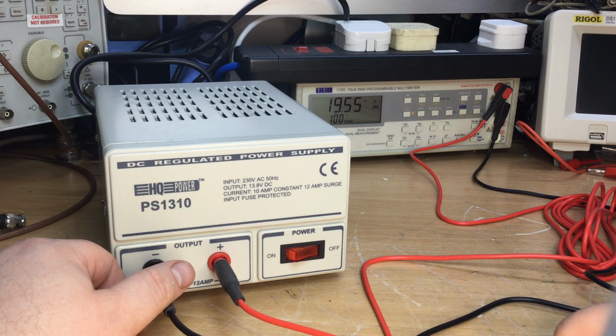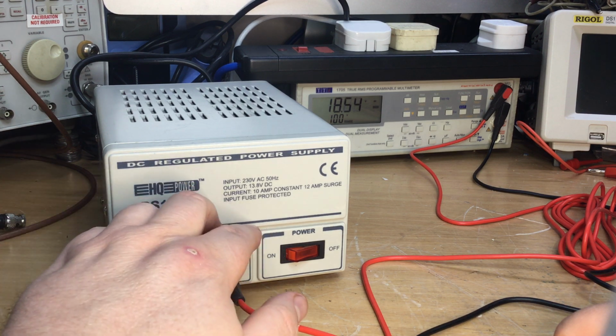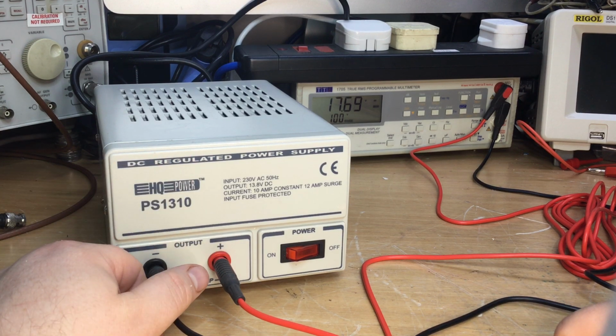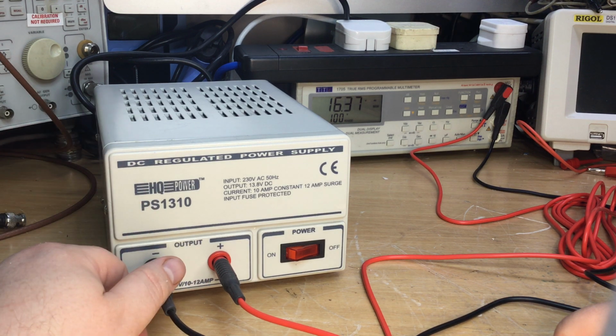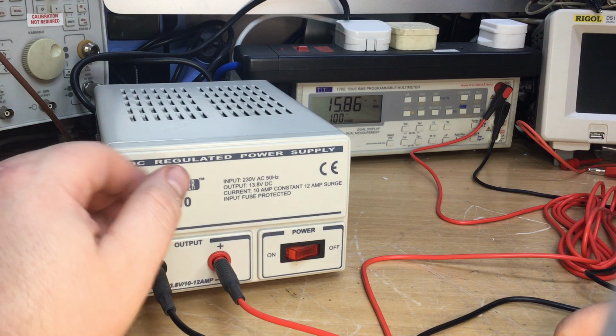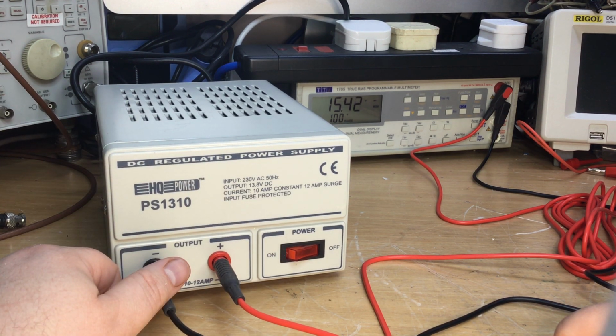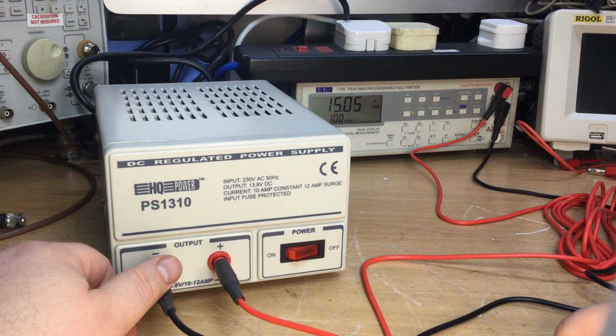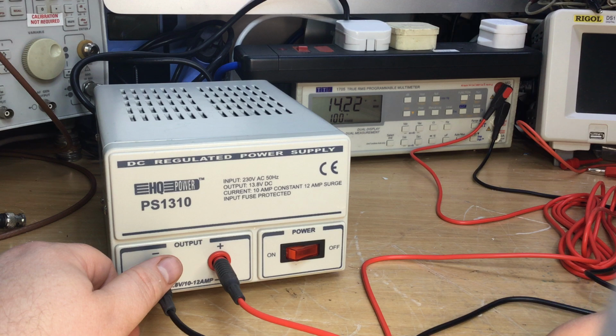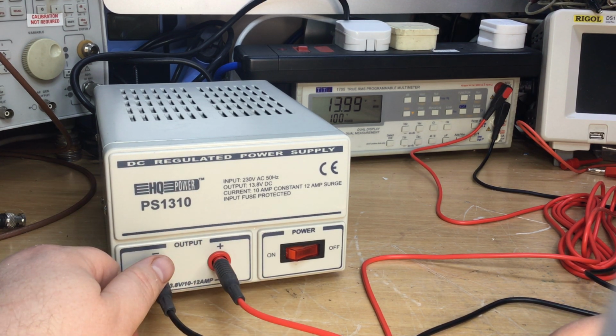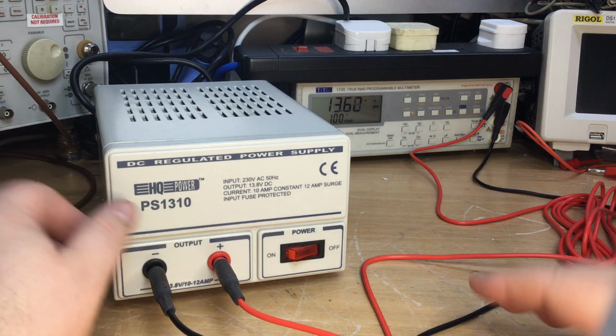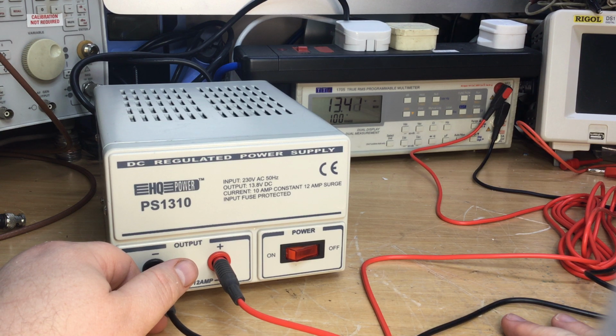Normally most power supplies with a fixed output have a protection crowbar circuit that triggers when the voltage rises above a certain level - about 15 volts if it's a 13.8 volt power supply - and it'll just short the output and pop the fuse. But this power supply, from what I can see, has not protected itself in that way. Even now the capacitors are just discharging slowly, and we're still at 14 volts even with the supply off for some time. So it looks like there's definitely an issue there - at least we've confirmed the fault the customer reported, which is high output voltage.